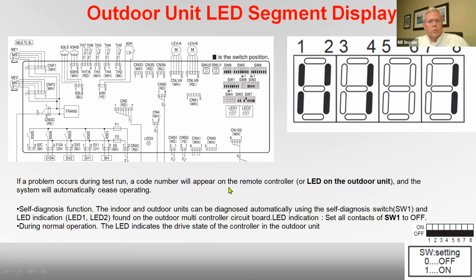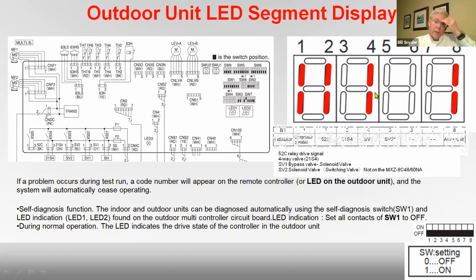Now here on the outdoor unit, remember I mentioned these LEDs a few minutes ago? This is the outdoor board. This is what you'll see when you look at the service facts. You'll see the linear expansion valves here. These are thermistors up here, the fan motors, just like the boards we just looked at. Right here, there's LEDs. There's 2 of them together and they kind of look like this right here.